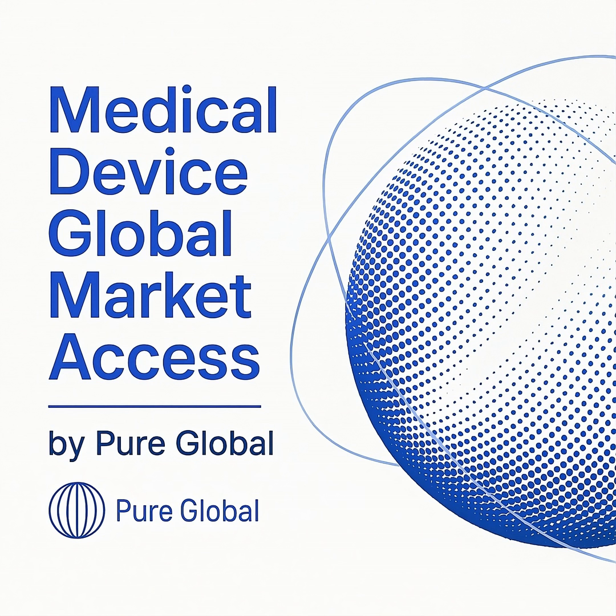When the time comes to transition to the UKCA mark, or if a manufacturer chooses to do so proactively, the process is similar to the CE marking process. It requires a conformity assessment to ensure the device complies with the UK Medical Devices Regulations 2002. For low-risk devices, this can often be a self-declaration of conformity. For higher-risk devices, the assessment must be conducted by a UK-approved body, which is the UK's equivalent of an EU-notified body. The technical documentation compiled for the CE mark serves as an excellent foundation. However, it must be reviewed and updated to ensure it references UK regulations.